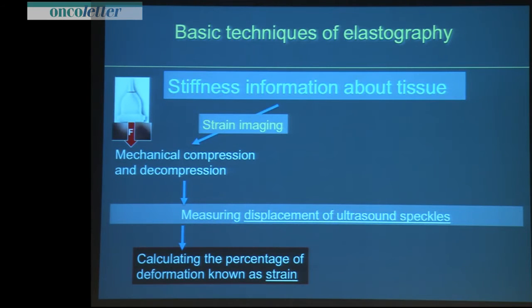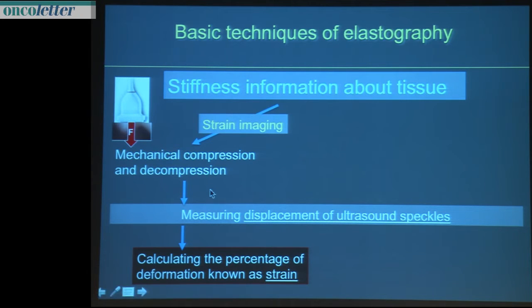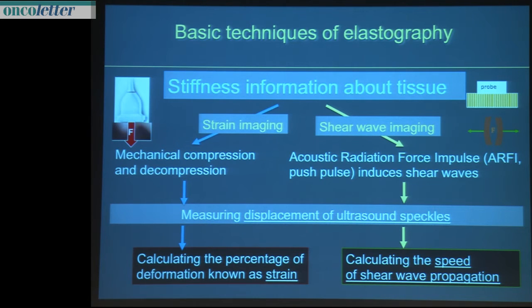We have two basic methods, and both measure the displacement of ultrasound speckles. However, the applied force is different. On one hand, it's mechanical compression and decompression. On the other hand, it's a shear wave that induces these small displacements. On one hand, the percentage of deformed length or distance is measured as strain. On the other hand, we are measuring the speed of shear wave propagation.